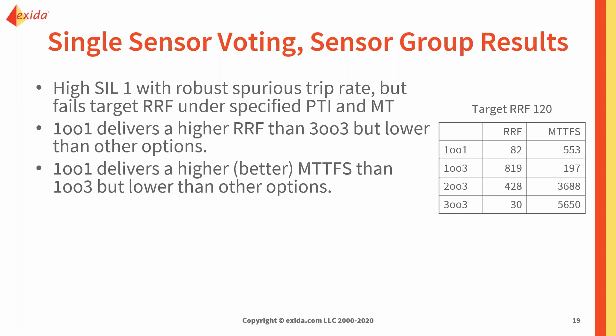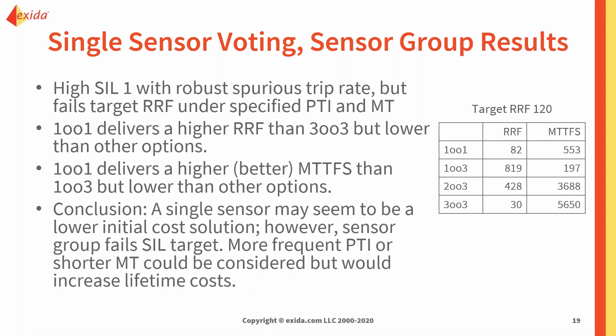Comparing the one out of three and the two out of three: with one out of three, we get the highest risk reduction factor but also the shortest spurious trip times. A single sensor may be an initial lower cost, but by the time we make changes to our process to try and reach our target, we'll probably increase costs elsewhere in the life cycle. So it probably makes more sense to move forward with the redundant sensors — using all three temperature transmitters.